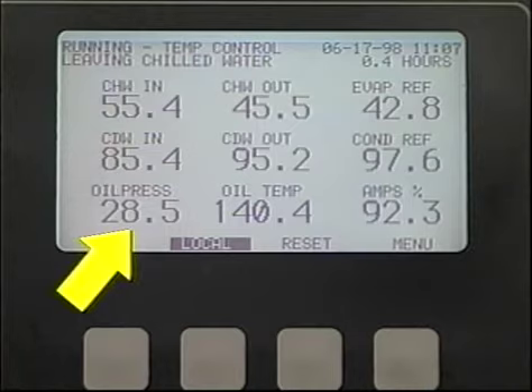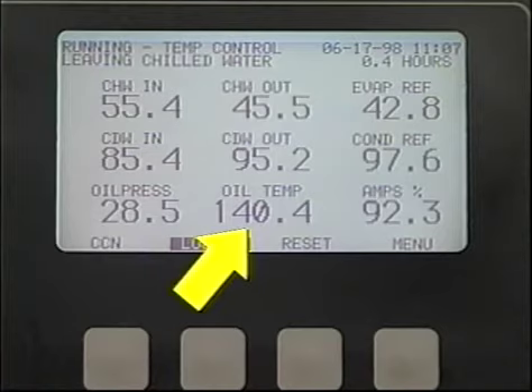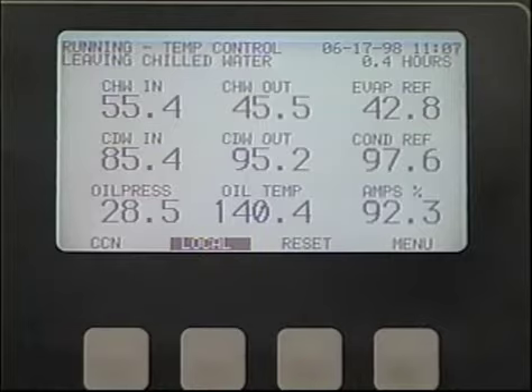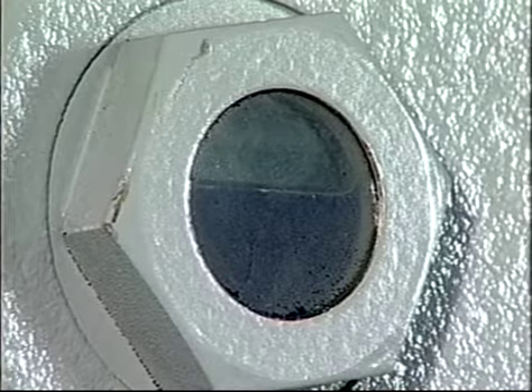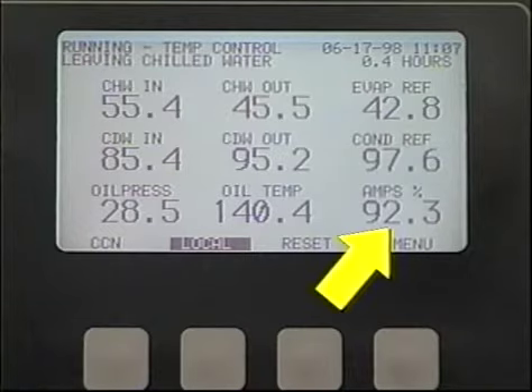Discharge oil pressure should be 18 to 30 psi above the oil sump pressure. The oil in the compressor sump should be 140 to 150 degrees Fahrenheit. The bearing oil return temperature is okay between 120 and 165 degrees Fahrenheit. The oil level in the sight glass should be visible anywhere in one of the two sight glasses, both when running and when shut down. Motor amperage is in percent of motor current that's being used. Always refer to the equipment's original design data for full load operating conditions.